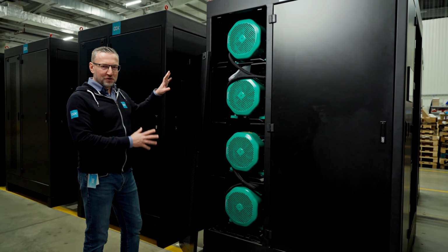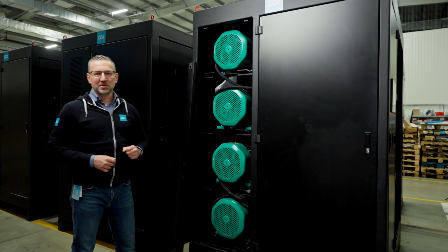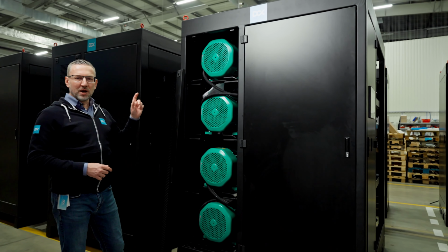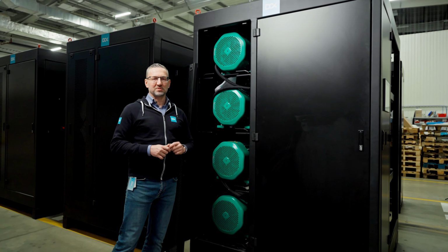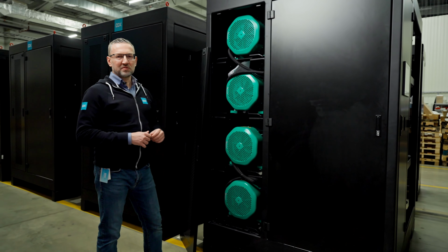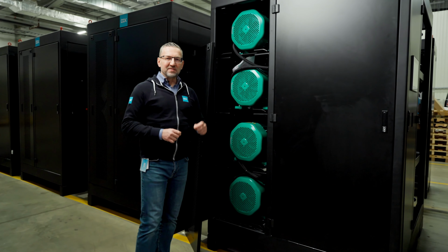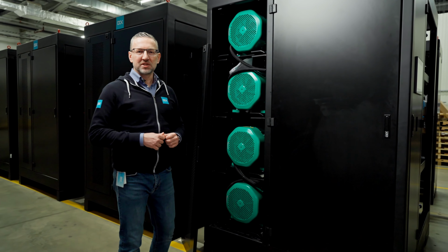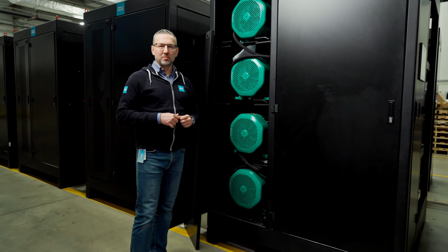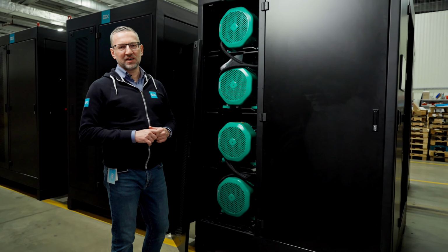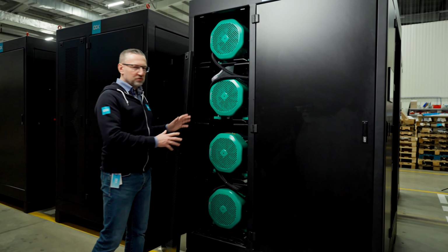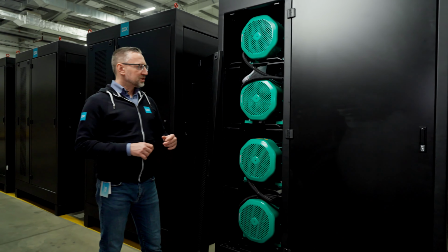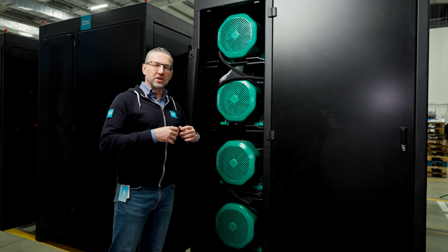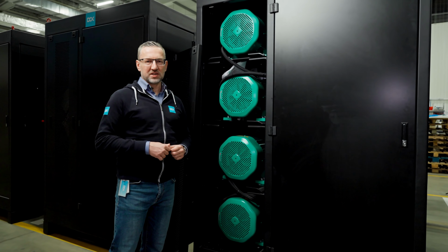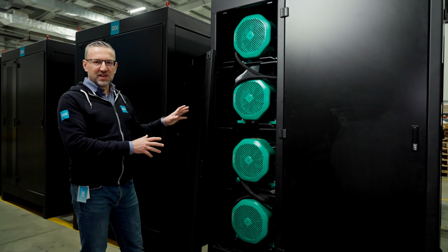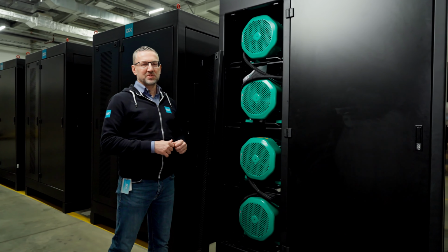4 pumps, 4 huge pumps, in an N+1 configuration. So we have 3 pumps operational, 1 pump as the N+1 spare. And those pumps provide huge capacity. It's over 11,000 liters per minute, which means 3,000 GPM, more or less, 660 cubic meters per hour. Huge flow rate at the right pressure, which allows us to provide cooling for tens or hundreds of racks actually. So that's the first hyperscale CDU system on earth.